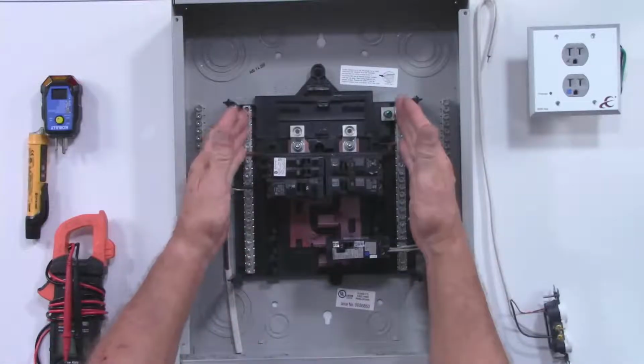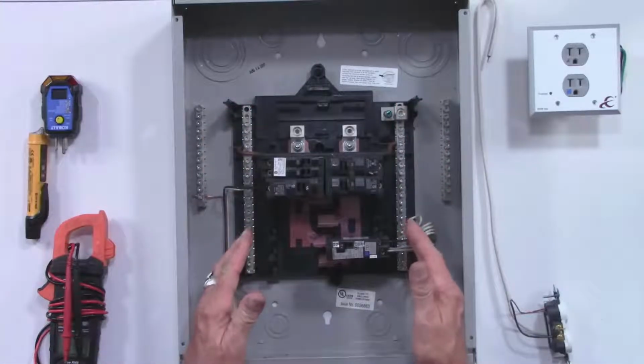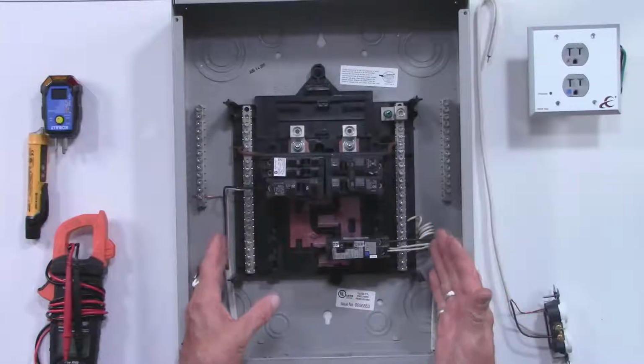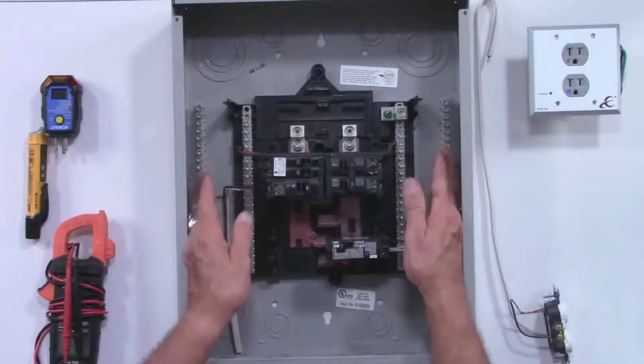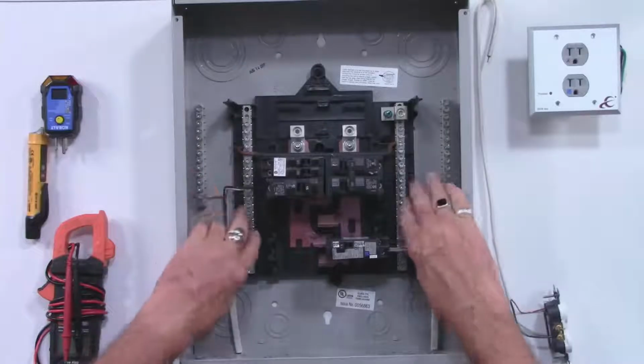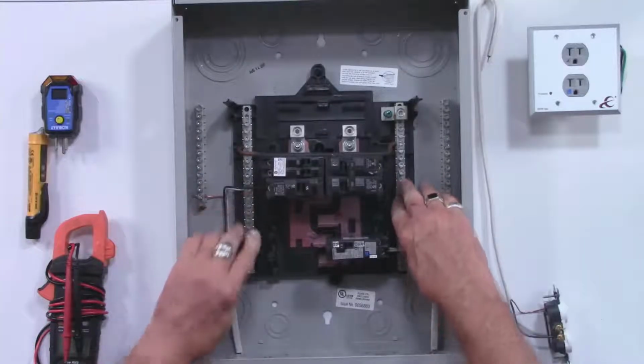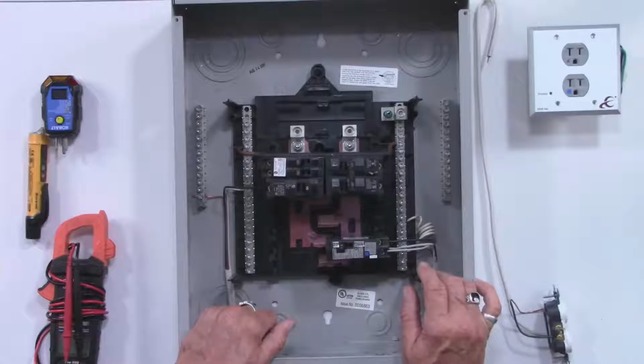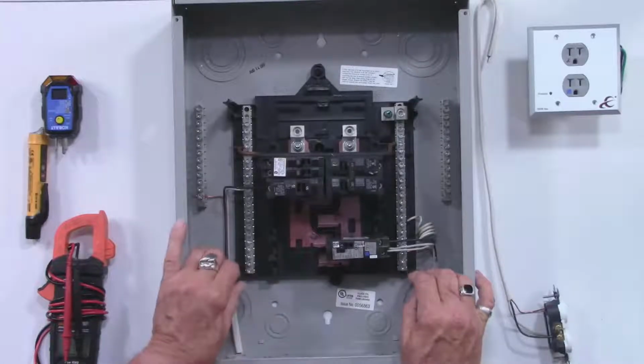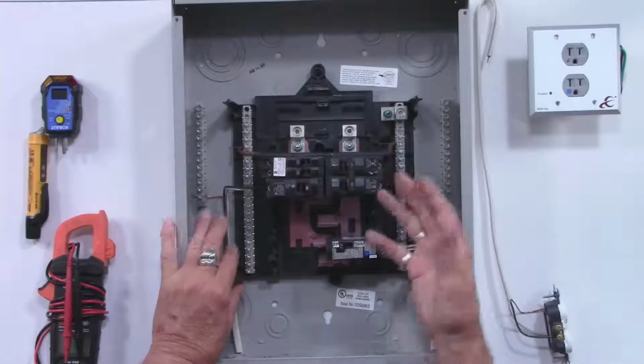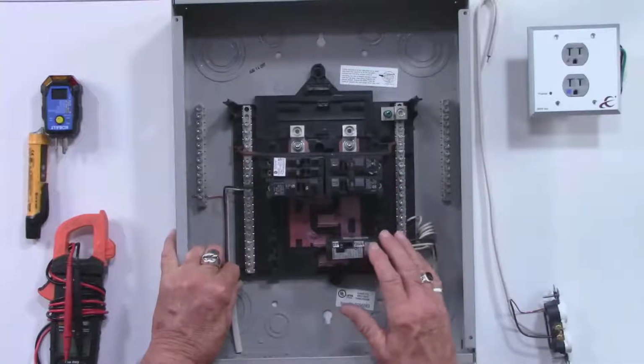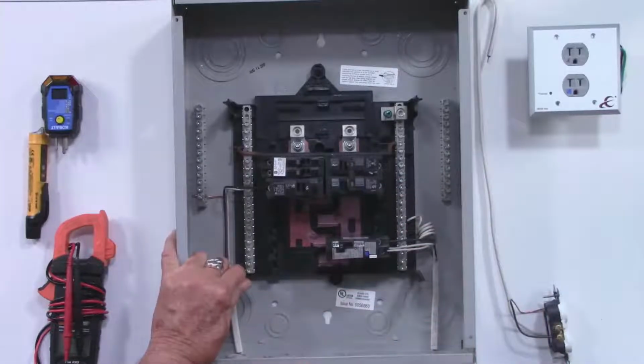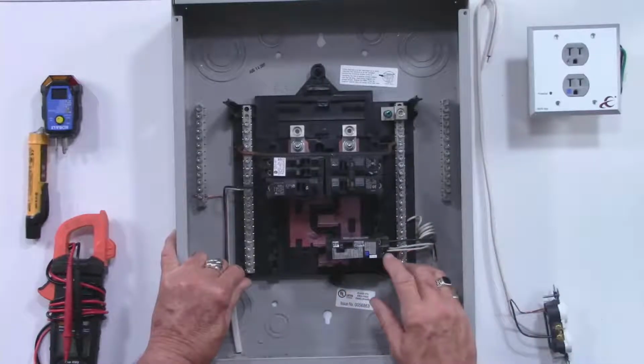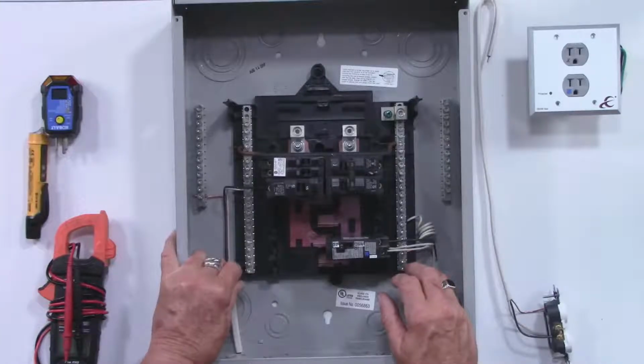And then here we have a panel that's set up, and this would be considered a sub panel because we are separating our grounds, which are these ground bars, and our neutrals. Now, before you go further, what is the difference between a ground and a neutral and an AC feed? Okay, on an AC feed, if you've got a black wire on your breaker and a white wire, the source takes the power out and the neutral brings the power back to the source again. The black or load line carries it to the device. Yes, the neutral is the return, so you get that alternating current.